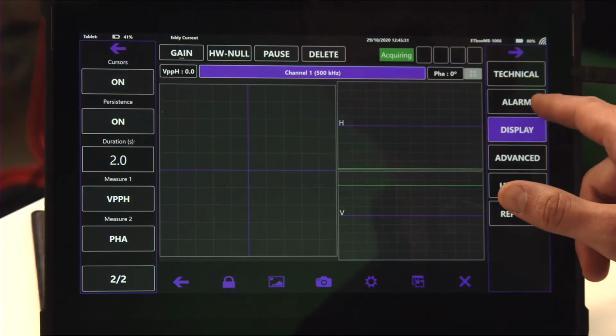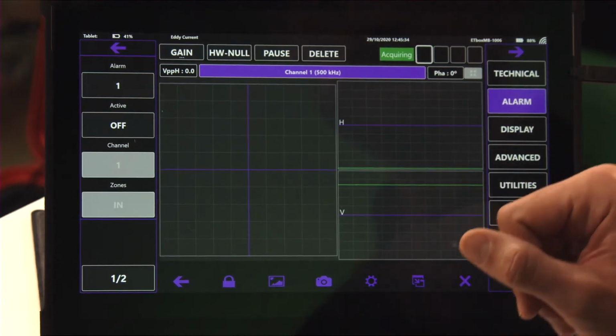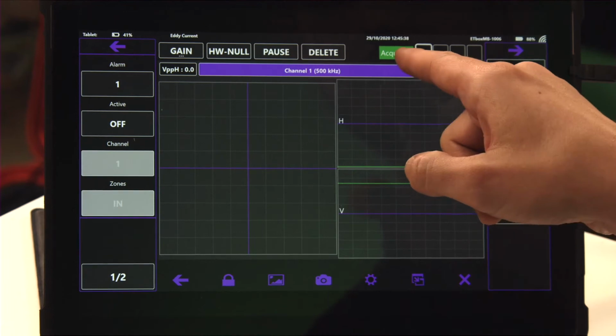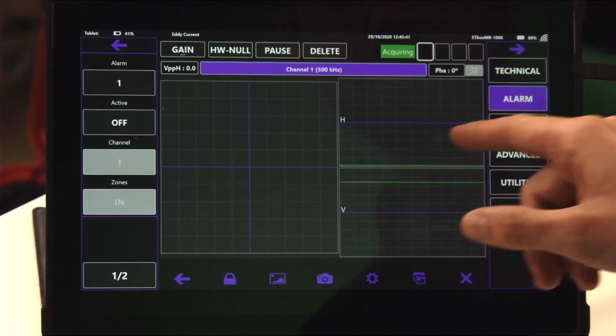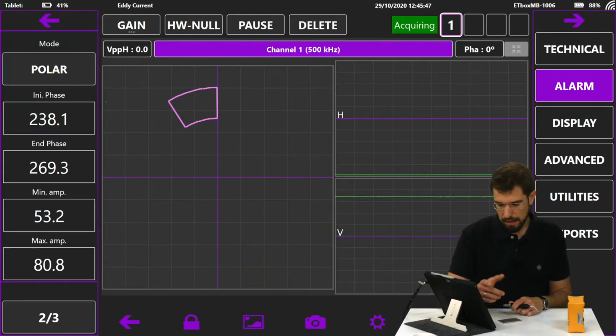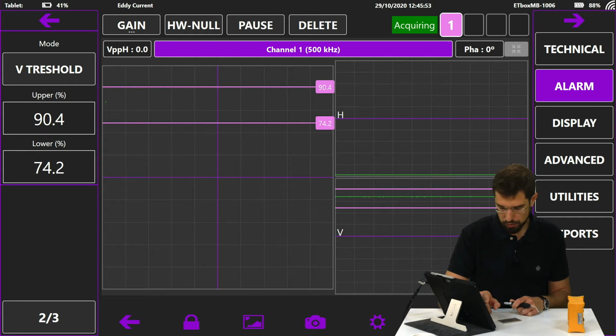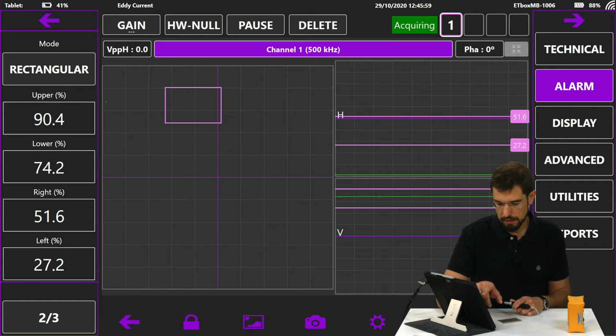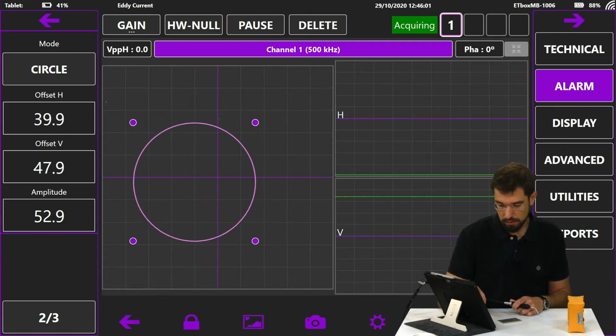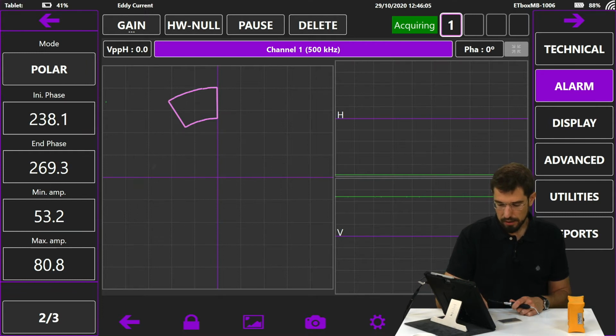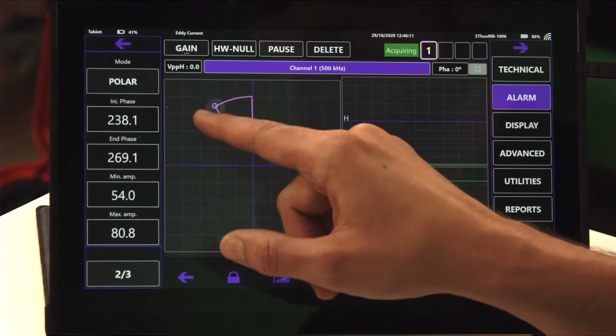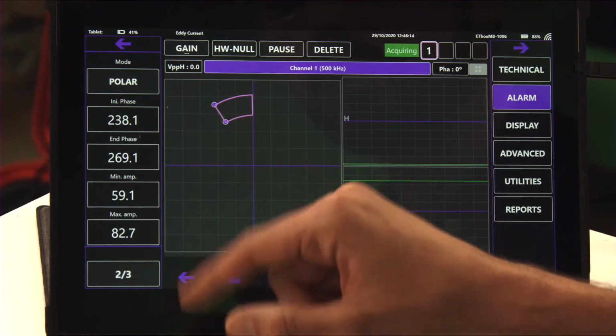Once we've seen that, we can talk about the tab that's on the alarm section. We have up to 4 alarms ready to be set up. In this case, they're deactivated, but we're going to activate them. Okay, we have several alarm modes. I have activated one that's the polar one, but you can also use thresholds, for example, horizontal, rectangular, circular, or polar thresholds. All of them are configurable via the touchscreen. We can enlarge them, reduce them, depending on the area of the impedance plane that we're interested in working with.